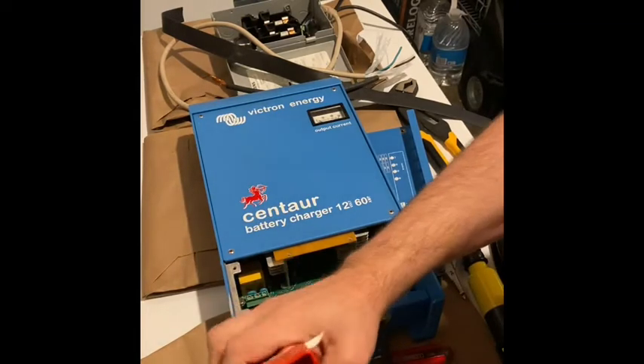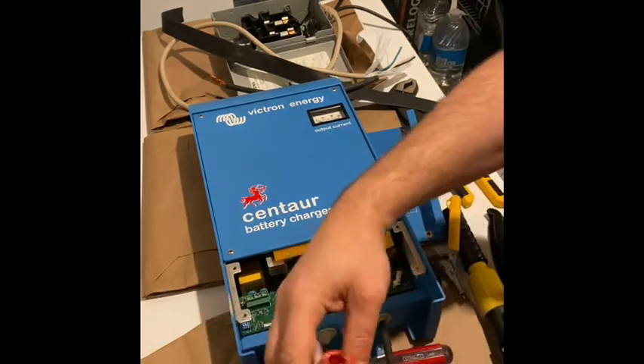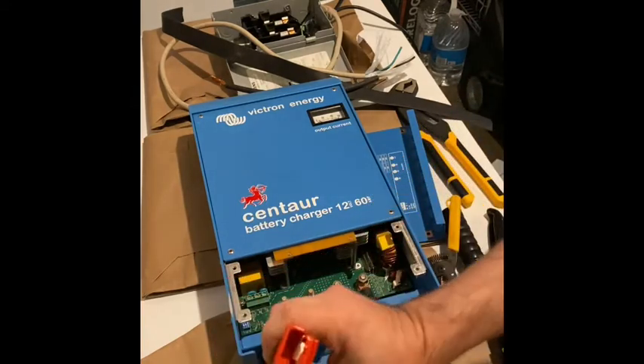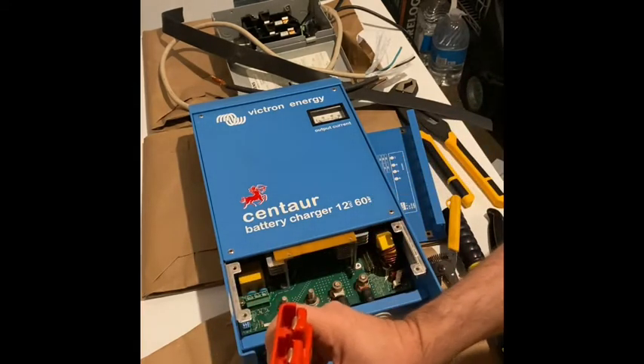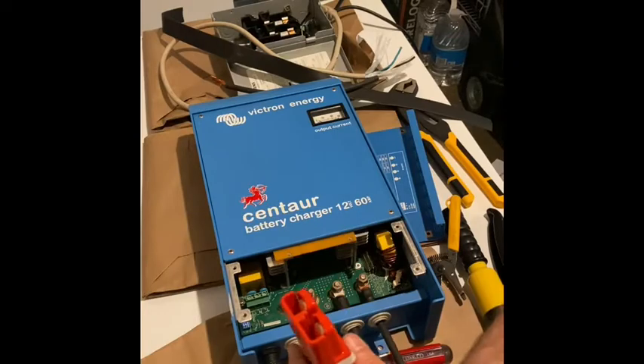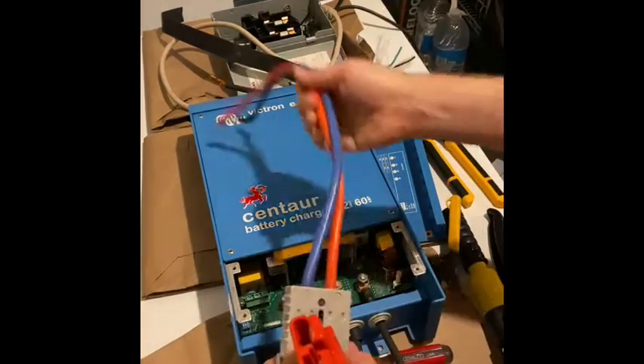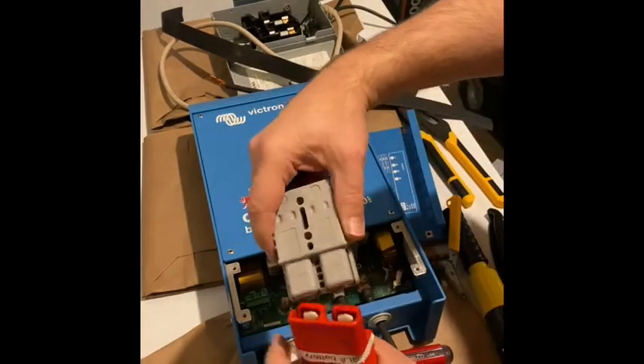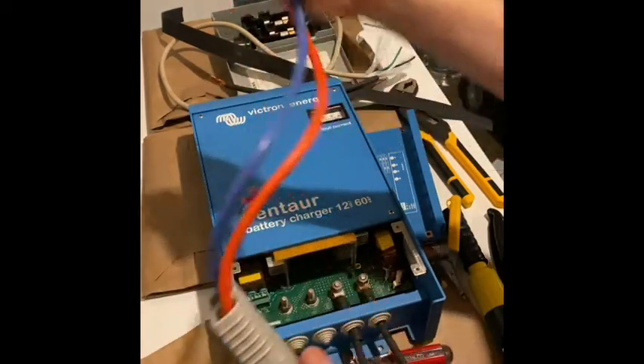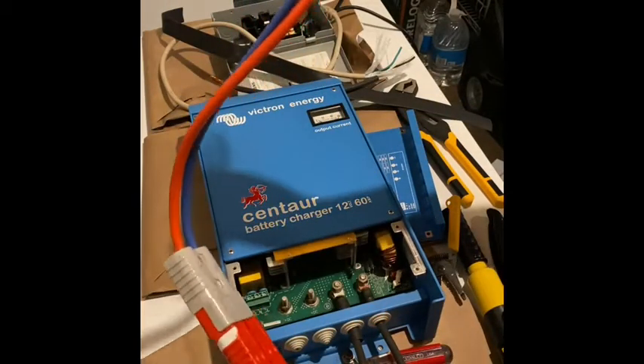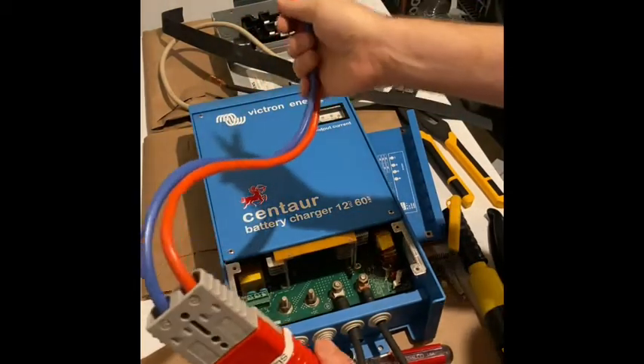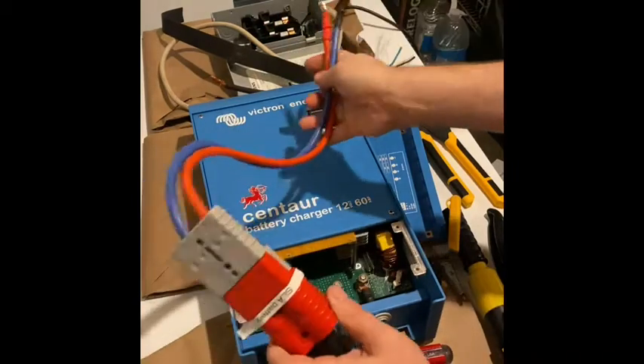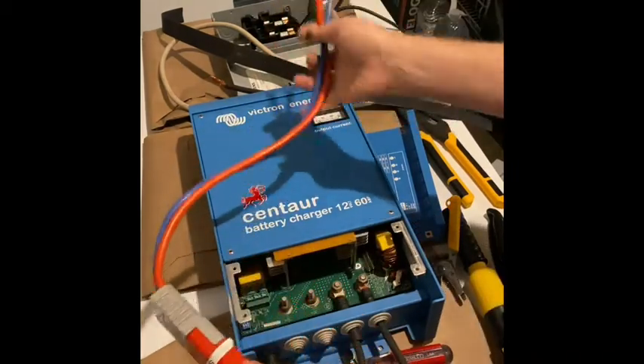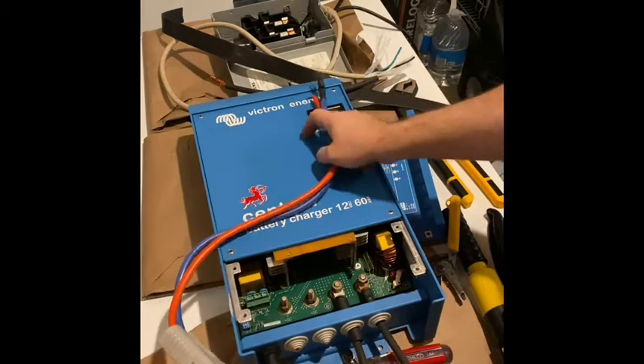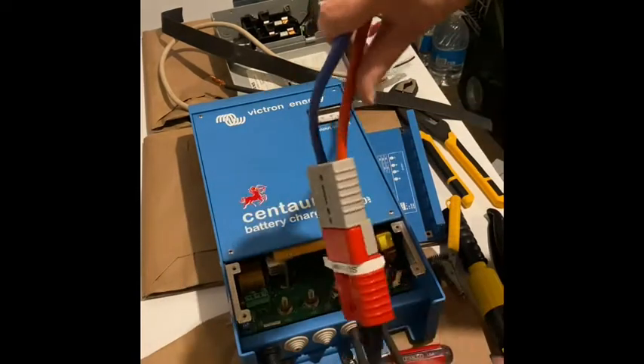There we go, the connector is ready, and it's got longer wire pigtails so it can feed the Centaur properly and go to the battery charge cable. This one will go to the battery array. These cables can easily handle the 60 amp max current, and the connector is good to 175 amps, so these should be able to handle the Centaur at full power.